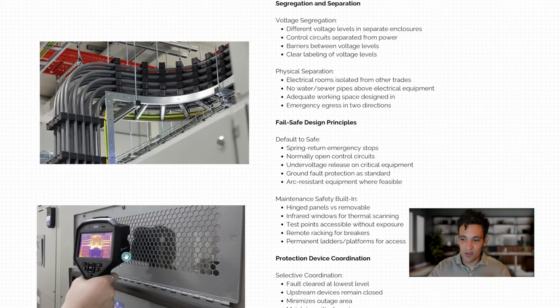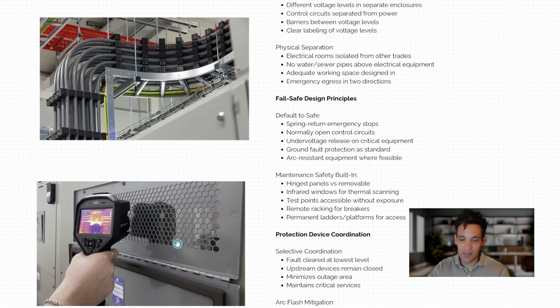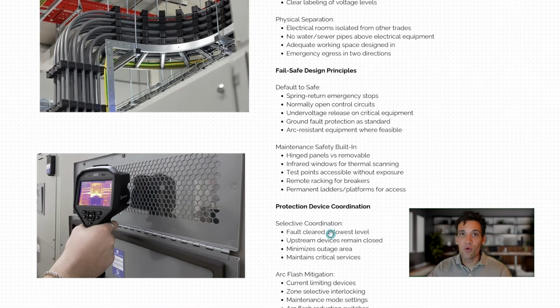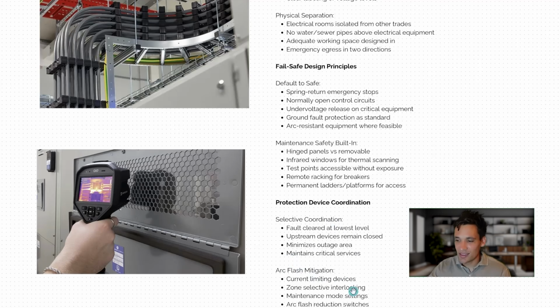The operations and maintenance of the system should be considered. For example, if you have to do checks for whether a circuit's in fault, there are infrared scanning windows rather than someone having to open the panel. You have test points accessible without exposure, and you can remotely rack and close circuit breakers. Everything's labeled, everything's really easy and safe to use. And finally, all our protective devices are coordinated and selected to clear faults at the lowest possible level, so that upstream devices can remain closed and the downstream devices trip first. We're minimizing the outage areas, and all the circuit breakers are also sized in accordance with the arc flash requirements.